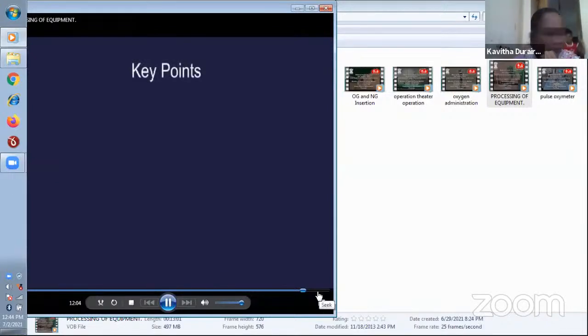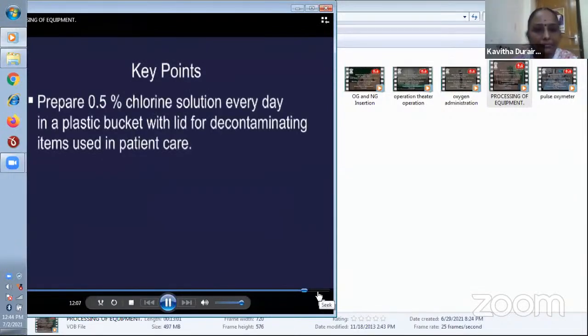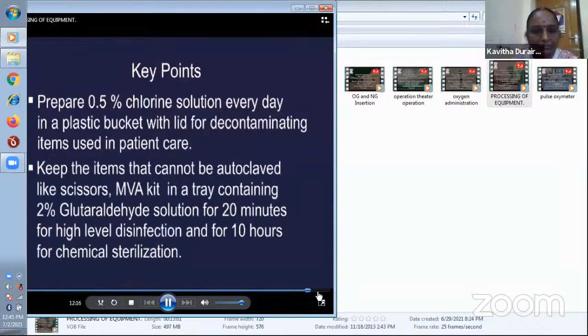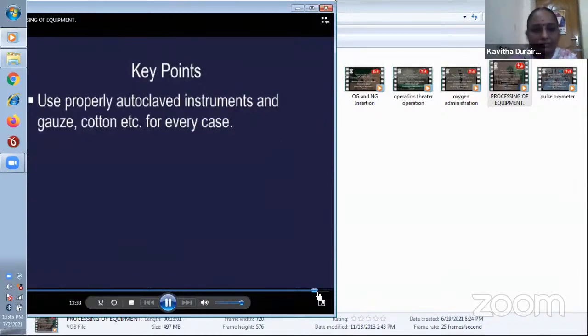Key points. Prepare 0.5% chlorine solution every day in a plastic bucket with a lid for decontaminating items used in patient care. Keep the items that cannot be autoclaved, like scissors and the MVA kit, in a tray containing 2% glutaraldehyde solution for 20 minutes for high-level disinfection and for 10 hours for chemical sterilization. Use properly autoclaved instruments and gauze, cotton, etc. for every case.